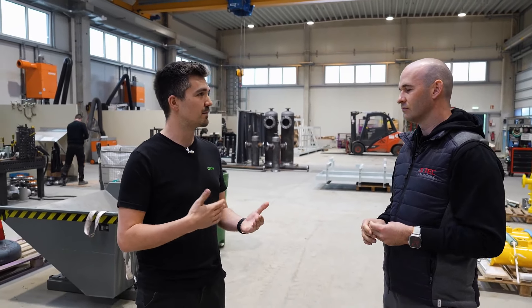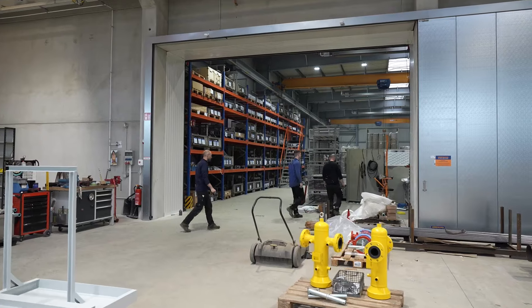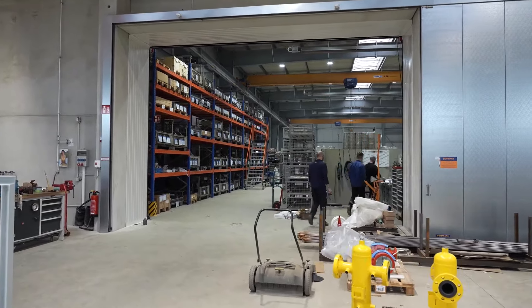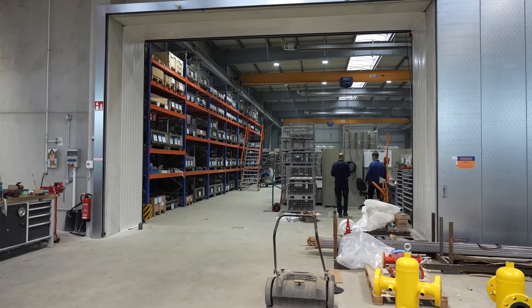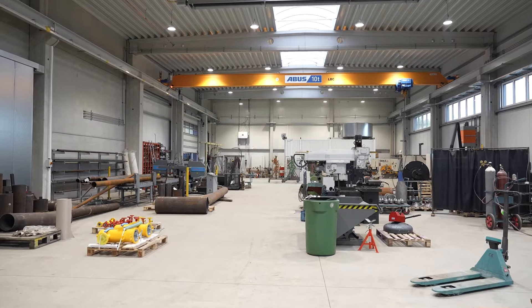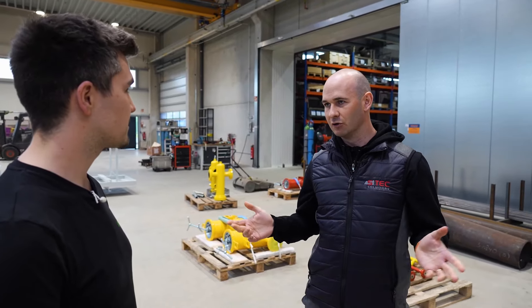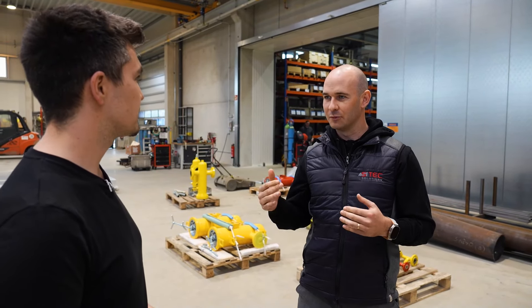Regarding the structure itself, you mentioned the electrics — a lot of new cables had to be installed. Is there a balance between using new cables and air technology? We have focused heavily on wiring because with such large distances and metallic influences, air technology is not suited here. The significant effort was pulling cables in the existing structure. In the hall it's relatively easy as you can lay cables along the existing cable trays, but in the office it needs to fit aesthetically, which took about two weeks and is now all done.